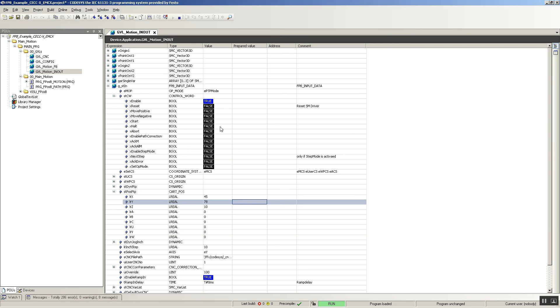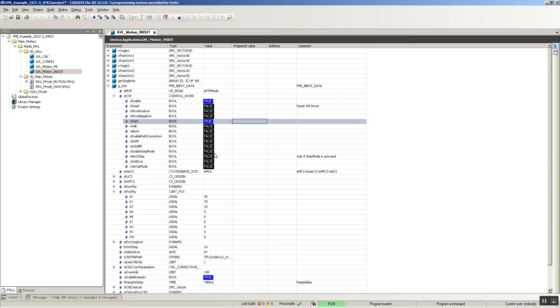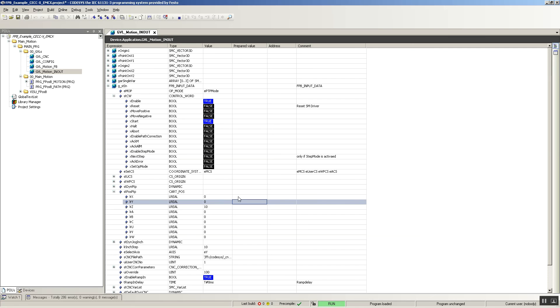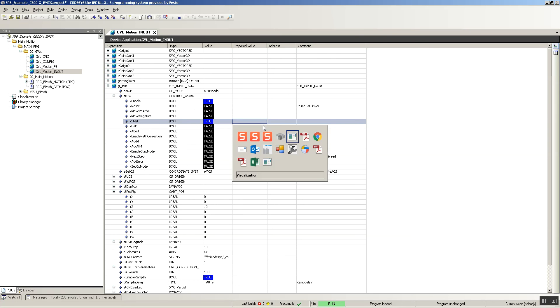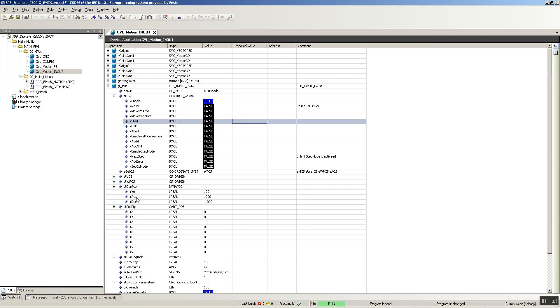I write those values and then I hit start, and I see the axis moving. Let's bring them back to zero — you need to set this bit back to false and then to true, and it moves back to zero. Now, if you wanted to change the speed, this is the dynamic point to point. You change here the acceleration, deceleration, and the velocity if you wanted to change the speed of the execution of that movement.